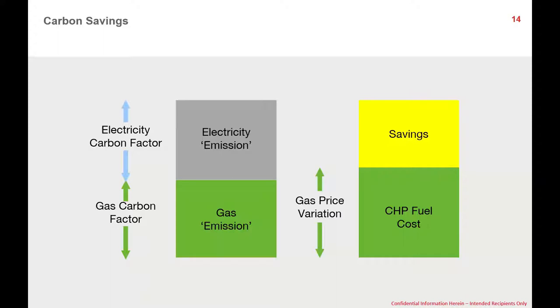We convert for high heating value, take into account net generation, and assume we're offsetting an 82% thermally efficient boiler. Then we only need to recover around 80% of the available heat from that particular engine to actually make a carbon saving. Now, certain schemes are more efficient than others and use the available outputs in different ways.